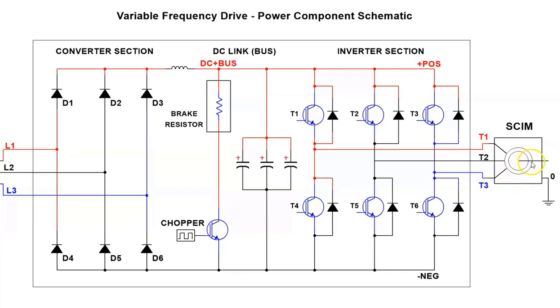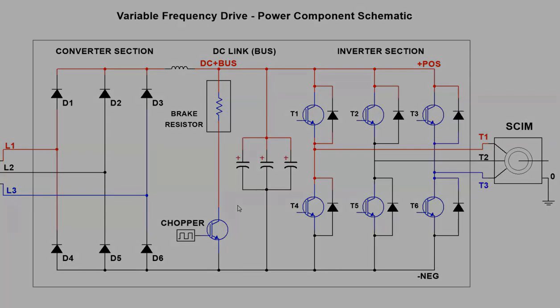And then you have what is called an overhauling load where the load is pulling the rotor and you have a more constant generator action where you have constant braking energy that you have to deal with. So I hope that explanation worked okay for you. You might have to go over the video a couple of times to get it to sink in. It takes a while to understand these concepts, but they are very, very important to understand when you are troubleshooting variable frequency drives.